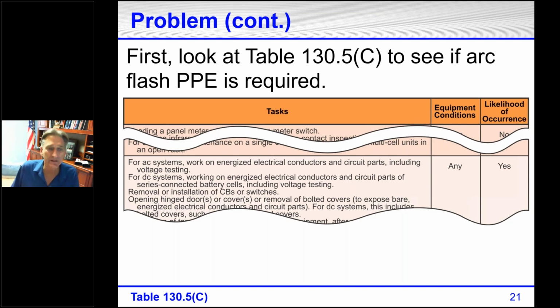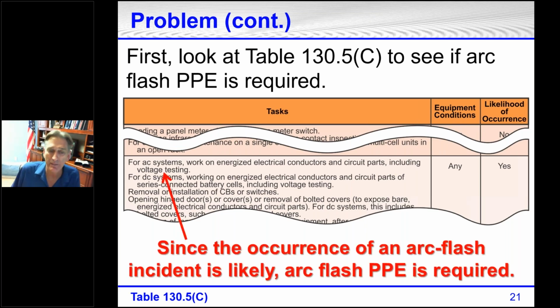130.5C says for AC systems, work on energized electrical conductors and circuit parts, including voltage testing. Equipment conditions, it doesn't matter what the equipment conditions are. It says the likelihood of occurrence is yes, meaning arc-rated PPE is required. If it says no, then arc-rated PPE is not going to be required. So yes, of course, there is a likelihood of occurrence. We knew this before looking at the table, but this just confirms it absolutely, because there are some tasks in here that maybe you're not sure of if they would need arc-rated PPE or not, so it is good to know where this table is and to know what's in this table.